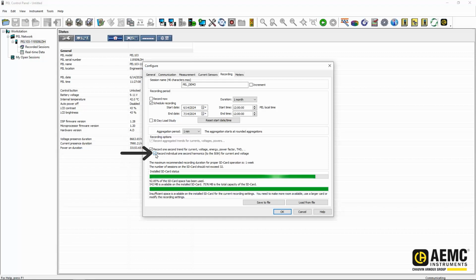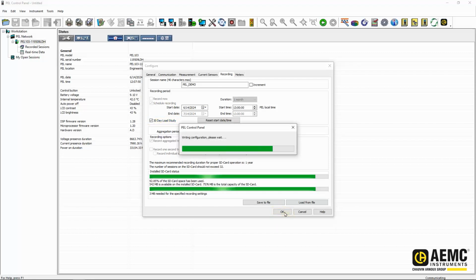Lastly, I can choose to record factorized harmonics in 1-second periods as part of my recording. Note that enabling both 1-second trends and harmonics increases the utilization of my SD card significantly. AEMC only recommends enabling these features if they are needed. Since we're configuring our PEL for a 30-day load study, I'm going to simply select the 30-day load study function and click OK to save my settings.